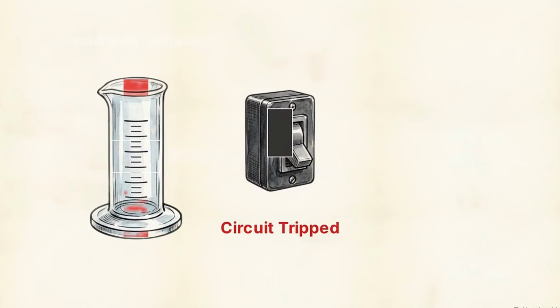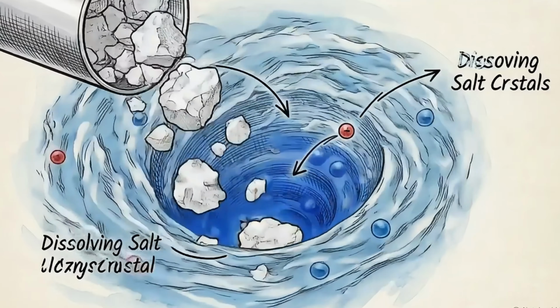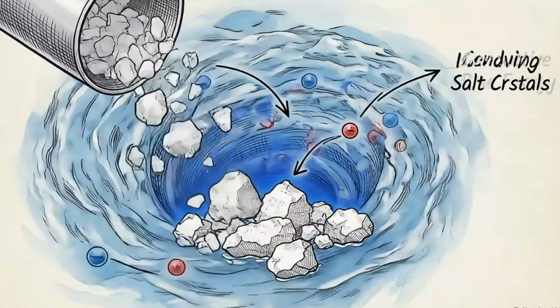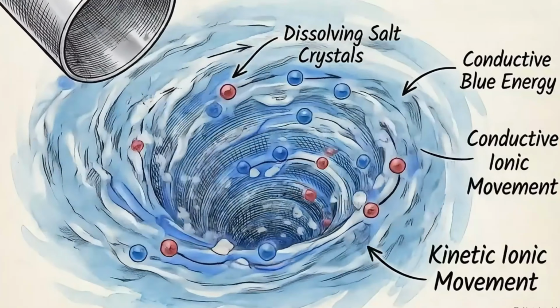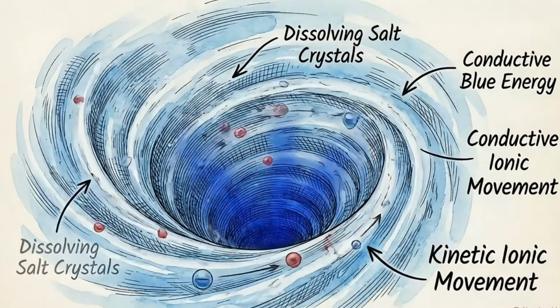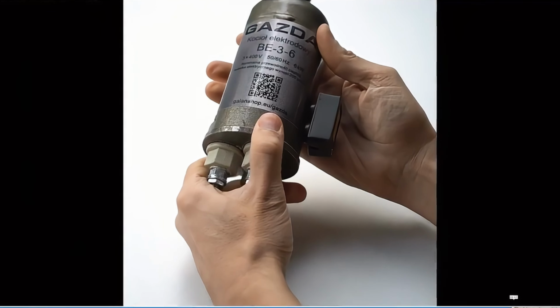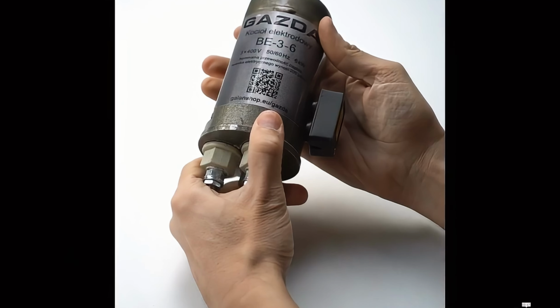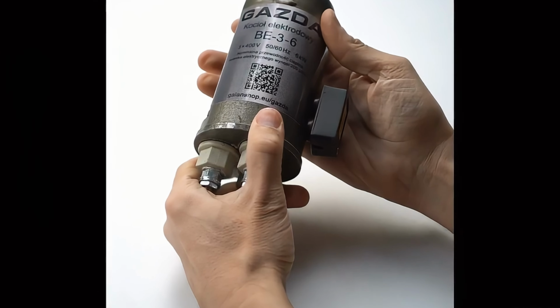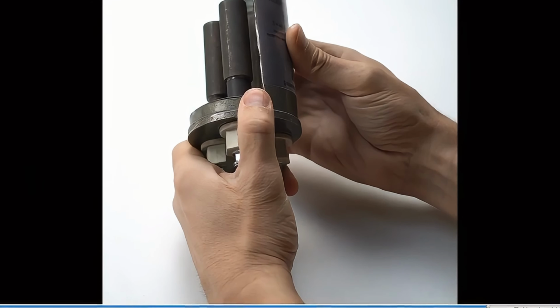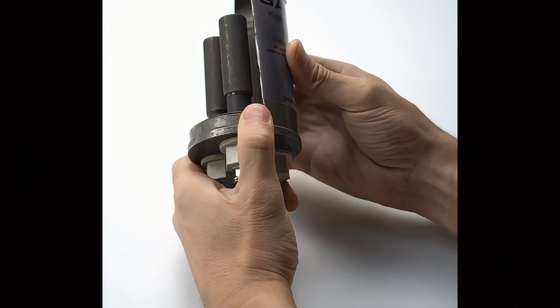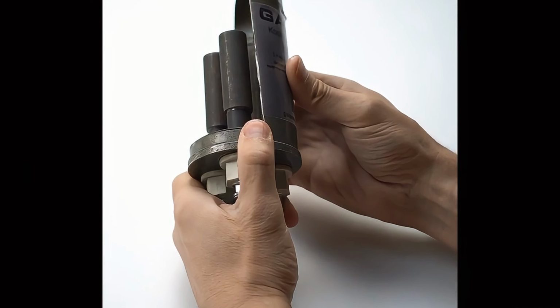If you use extremely hard, mineral-rich well water, the conductivity spikes too high, drawing excess current and tripping the circuit breakers. These dissolved mineral salts turn common tap water into the primary electrical conductor required for the boiler to operate. To see how this works, we have to look inside the hardware. From the outside, the unit is a heavy, compact industrial cylinder. At the base, standard electrical connections feed directly into a set of electrode rods that mount securely up into the main chamber.